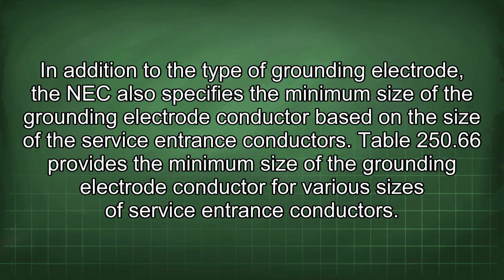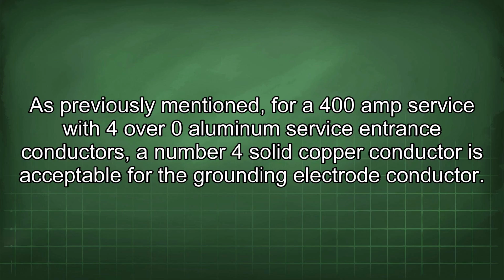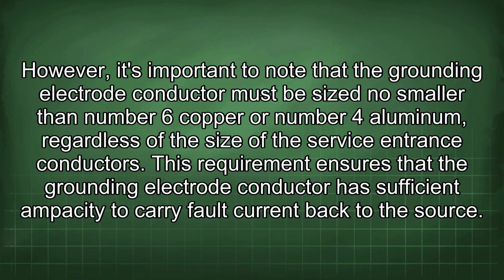Table 250.66 provides the minimum size of the grounding electrode conductor for various sizes of service entrance conductors. As previously mentioned, for a 400 amp service with 4/0 aluminum service entrance conductors, a number 4 solid copper conductor is acceptable for the grounding electrode conductor. However, it's important to note that the grounding electrode conductor must be sized no smaller than number 6 copper or number 4 aluminum, regardless of the size of the service entrance conductors. This requirement ensures that the grounding electrode conductor has sufficient ampacity to carry fault current back to the source.